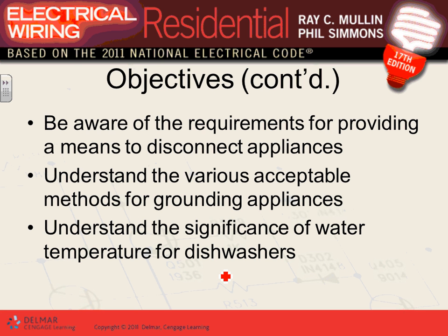All appliances and all motors require a disconnect, like we said yesterday. So you have to have a disconnect, and the reason for the disconnect is that you are sticking your fingers into the garbage disposal to clean it. You would hope nobody is going to flip the switch on and turn that garbage disposal on, and then you leave a few of your fingers down there. That's really what the disconnect is. Safety feature. All appliances require a disconnect. We'll talk about this one.